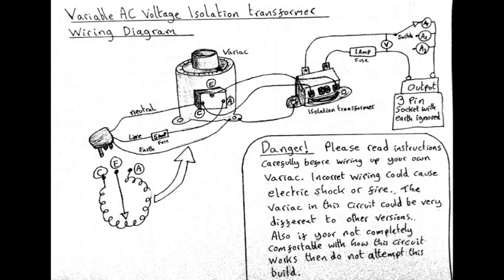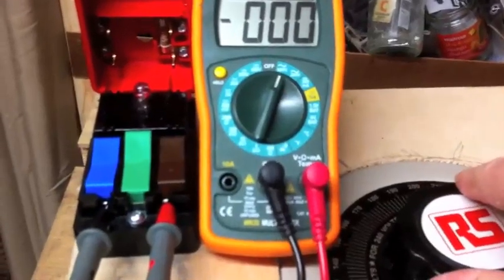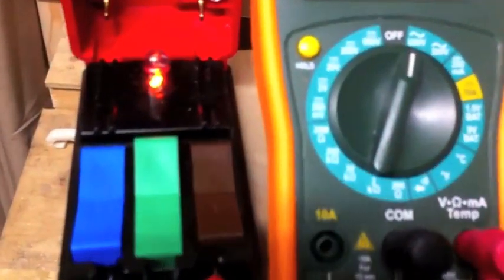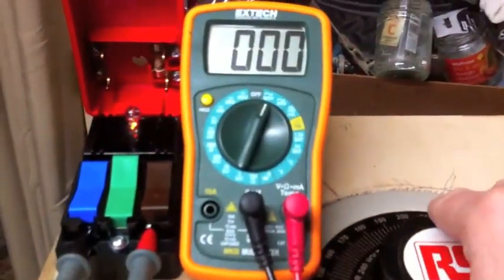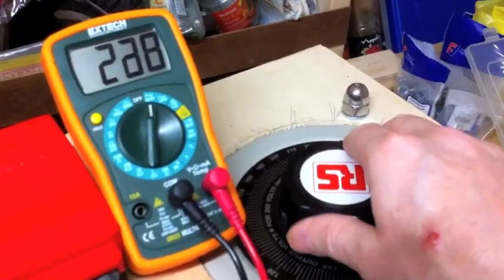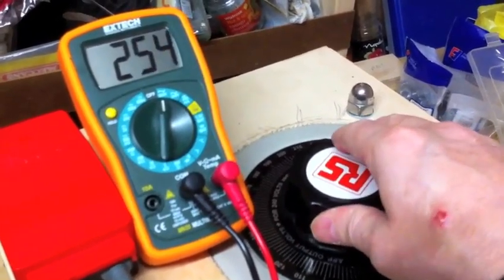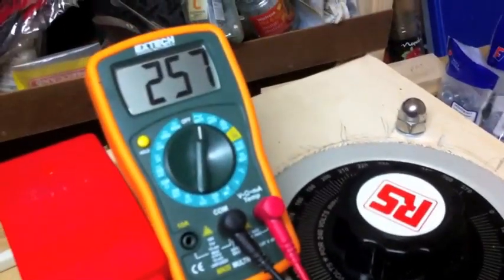Once you've wired everything up, before connecting your ammeters and everything else, you want to make sure everything's working correctly with the voltage. I've turned it on here, and I'm testing that safety red button - it's a safety throw button, and when it's up it shows the bulb but it's not actually live. When I close that red button, I can start seeing the voltage, and I'm turning the voltage up now just to check it's working. You can go above 240 volts - it gets up to 257, because the winding is a bit further along, giving that extra voltage.